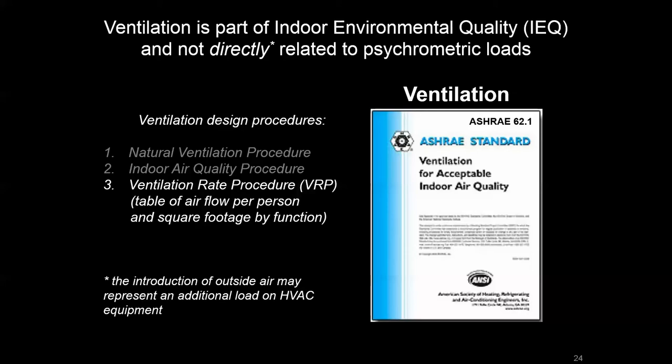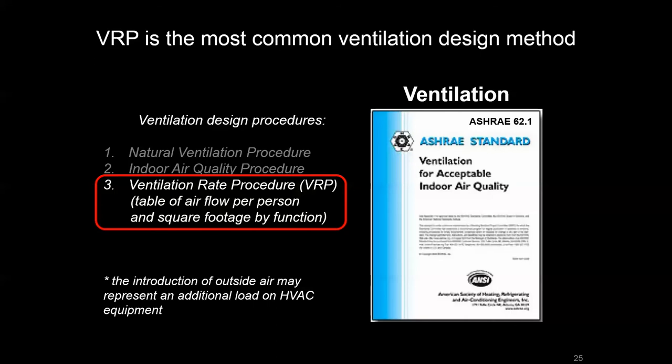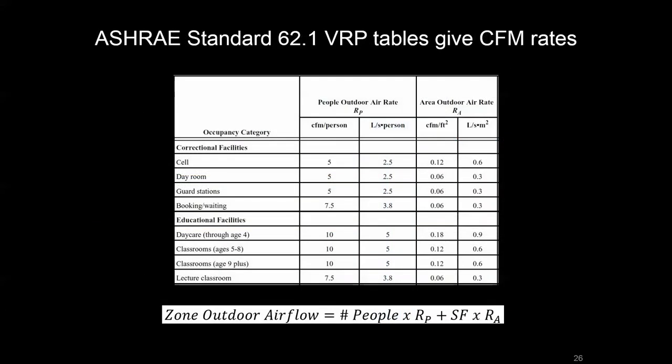The VRP is a more basic way of determining ventilation requirements based on space type, space size, and occupancy. It's really the powerhouse for ventilation design and can be used for quick checks to understand if a zone is under- or over-ventilated. Here's an excerpt from ASHRAE 62.1 — there are a number of space types listed with CFM per person and CFM per square foot factors. You apply those factors to the number of people and square footage in your space to get your zone outdoor airflow, then back into the percentage of outdoor versus recirculated air at your economizer.